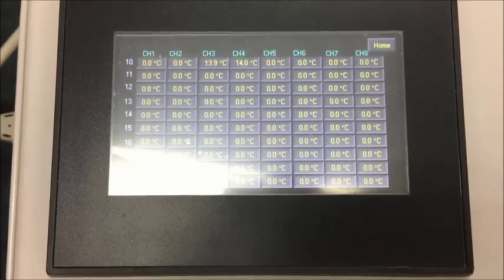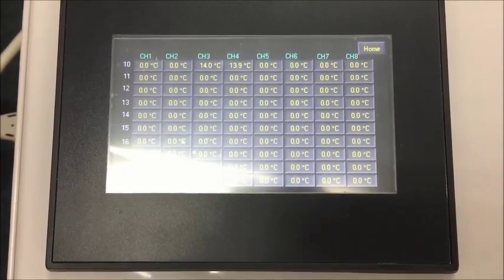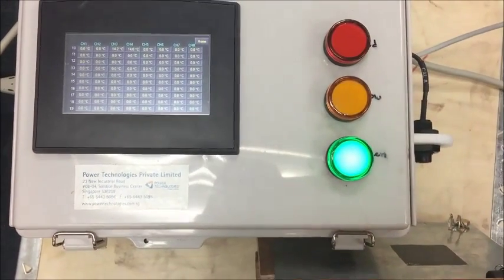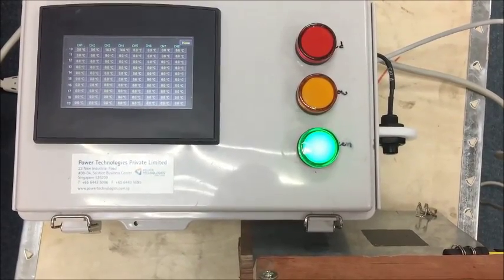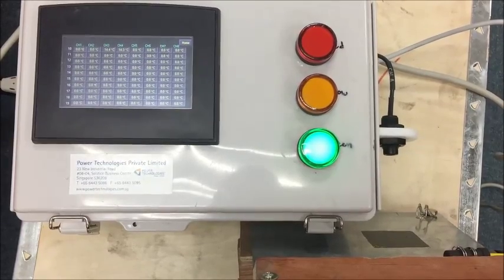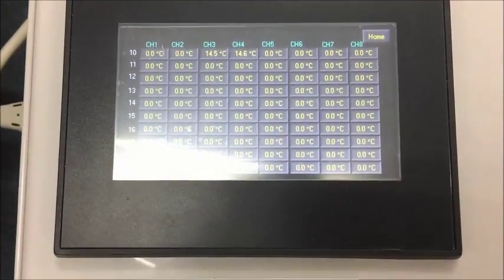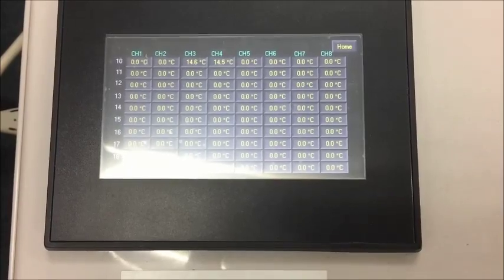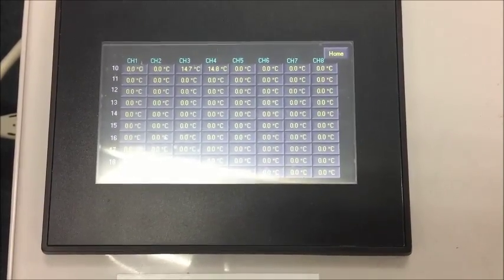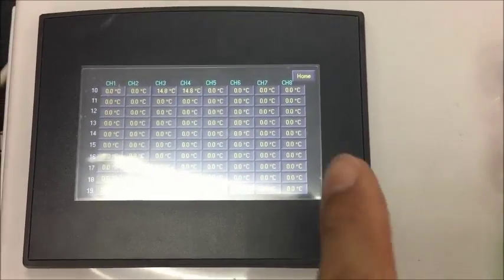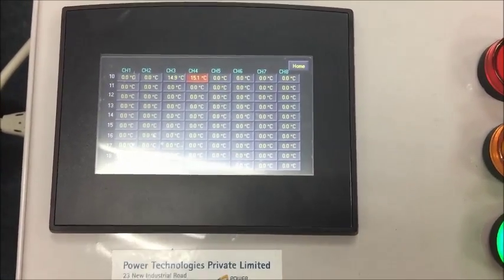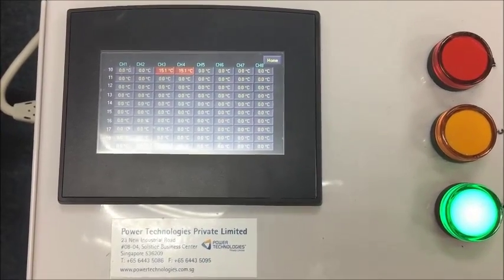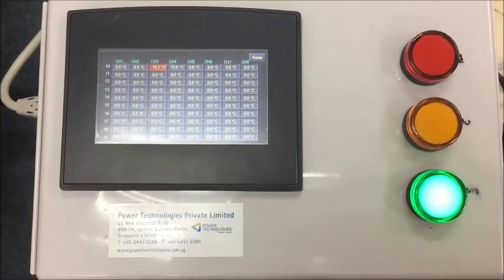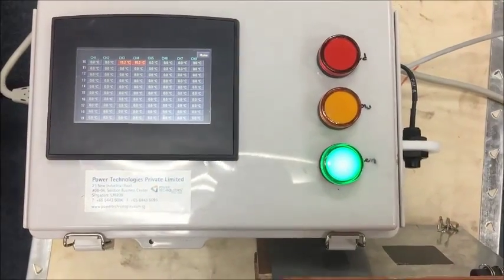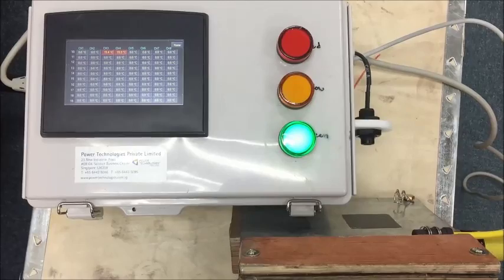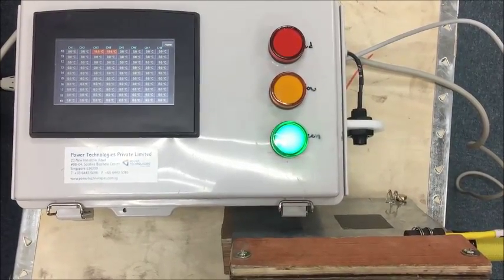So it reaches 13.9 delta T difference. Our system will never create any false alarm, as I mentioned. Remember, the 15-degree delta T is a warning alarm. You see when it's up and when it's down, so you won't get a false alarm immediately, because sometimes it may be due to a transient for a short period of time, then it goes down. So you won't get any false alarm until the system holds and detects for at least a minute, then the warning alarm will be activated. As mentioned, this is to prevent any false alarm.